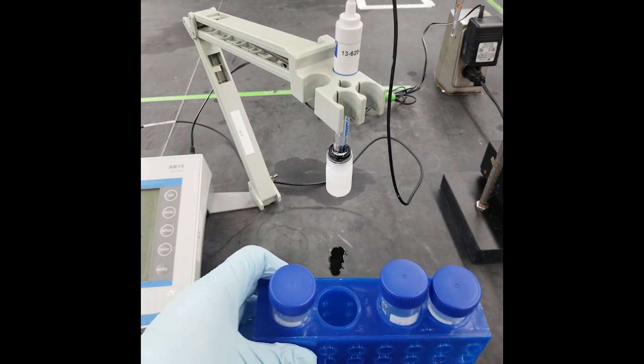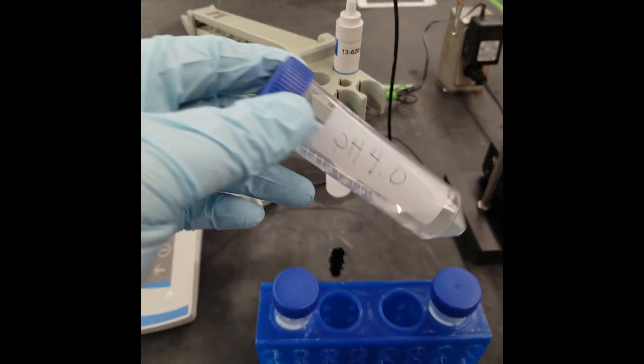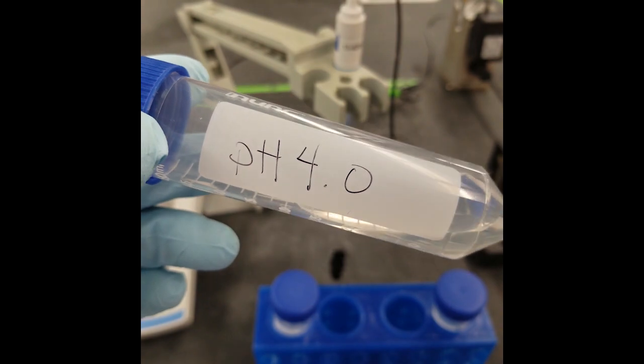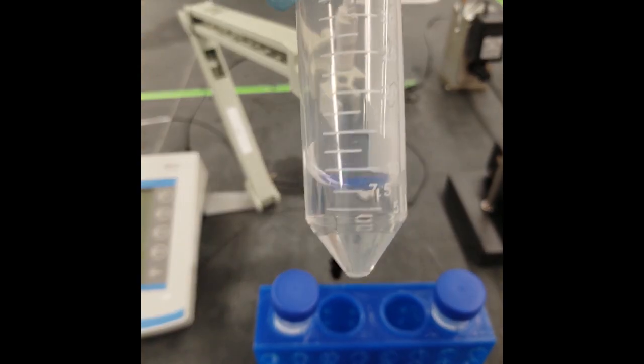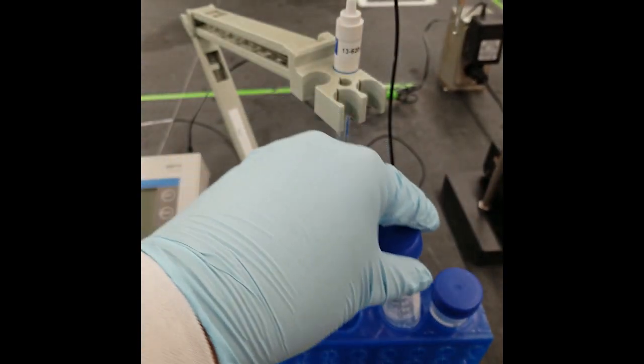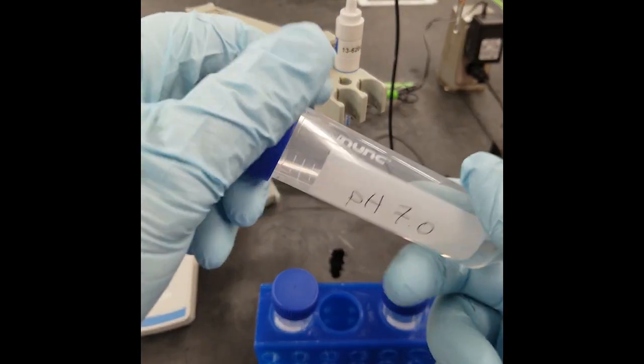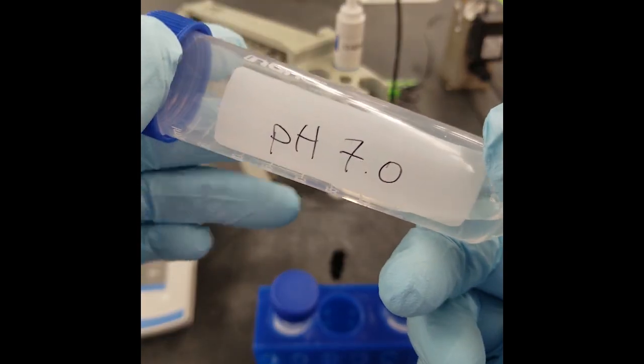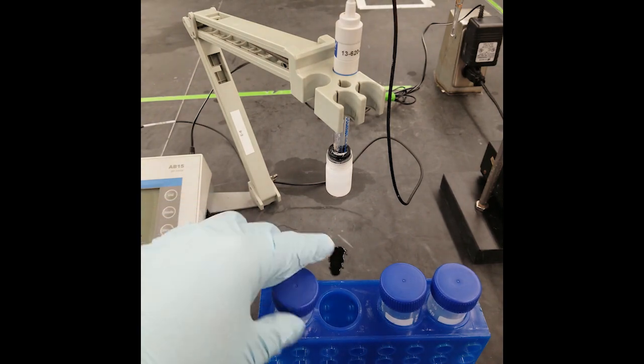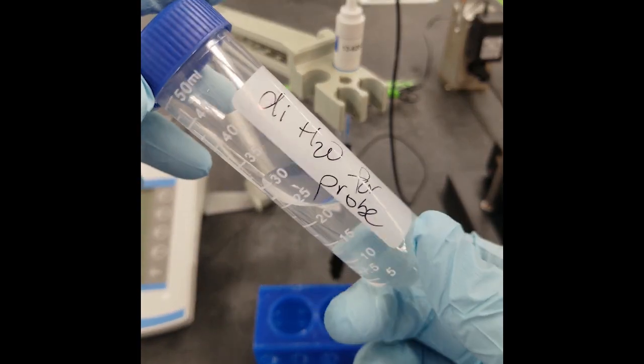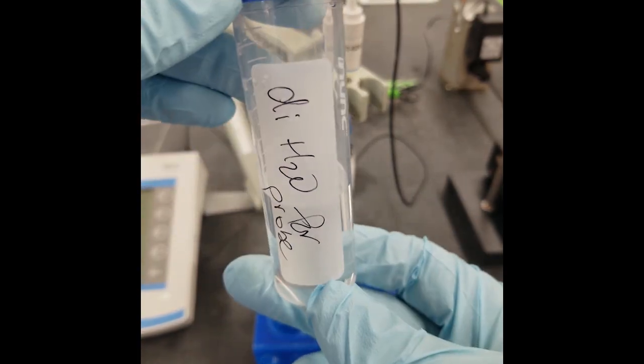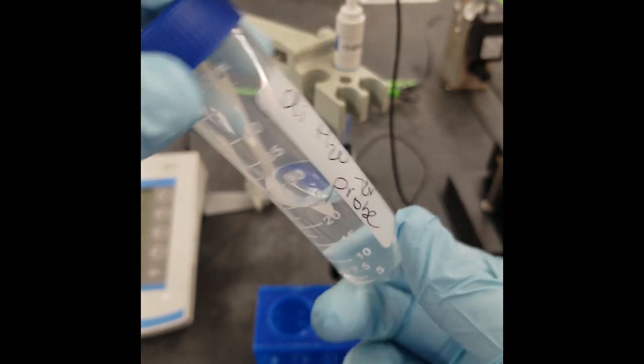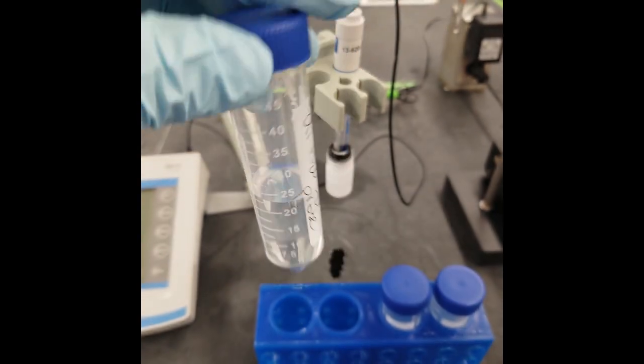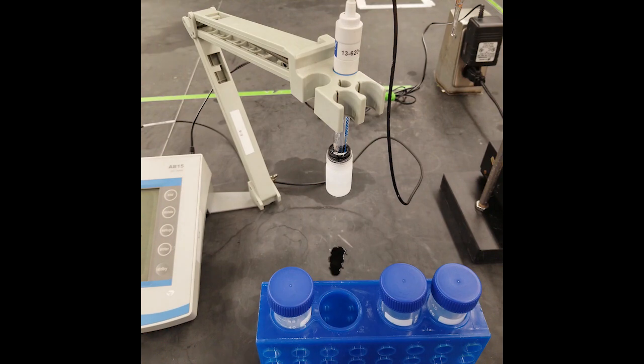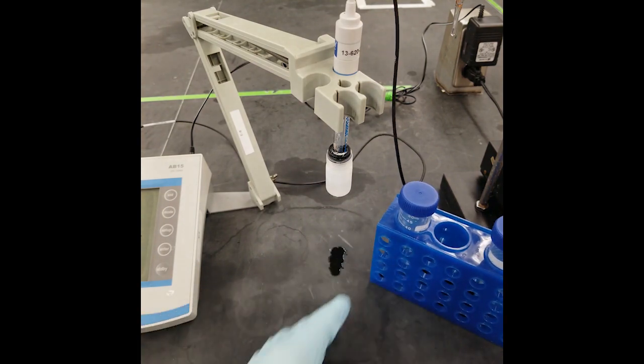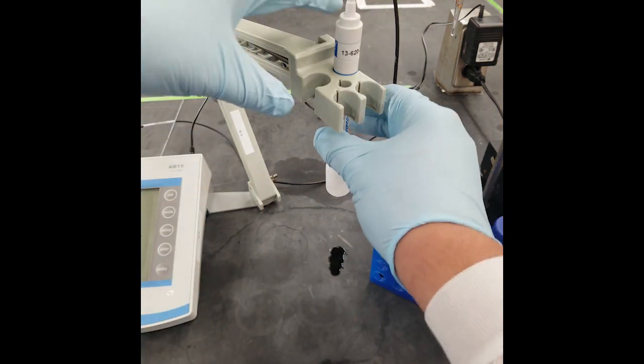So what you're also going to gather to get ready for your pH measurements is your pH 4 standard solution. Here I have 10 mL of this solution in a 50 mL conical tube, as well as a pH 7 standard solution. Also here, I'm showing you that I have about 25 to 30 mL of DI water in a 50 mL conical tube, and I'm just going to use this as a storage solution for when I'm not actively using the probe, so that the probe itself doesn't dry out.